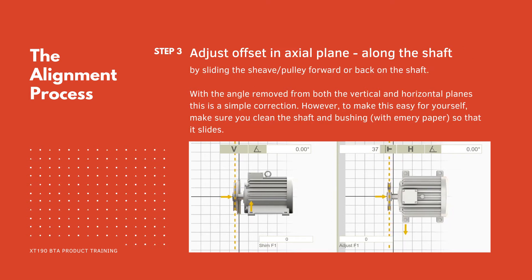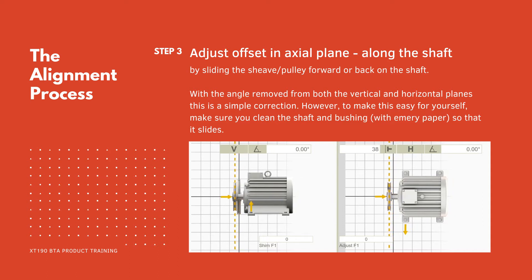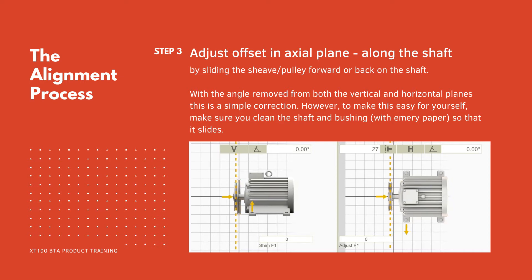Step 3: adjust the offset in the axial plane along the shaft by sliding the sheave or pulley forward or back on the shaft. With the angle removed from both the vertical and horizontal planes this is a simple correction. However, to make this easy for yourself, make sure you clean the shaft and bushing with emery paper so that it slides.